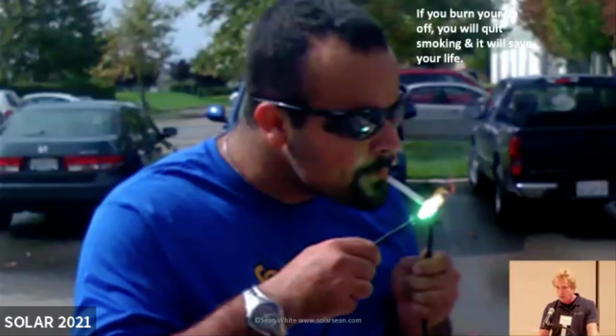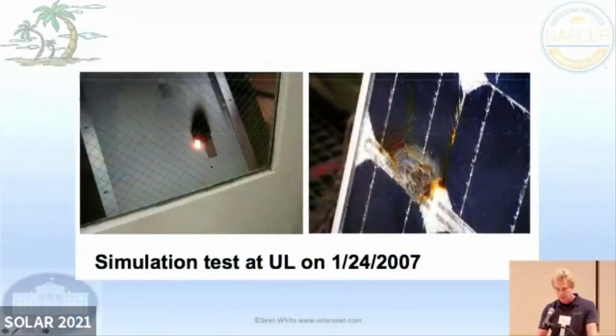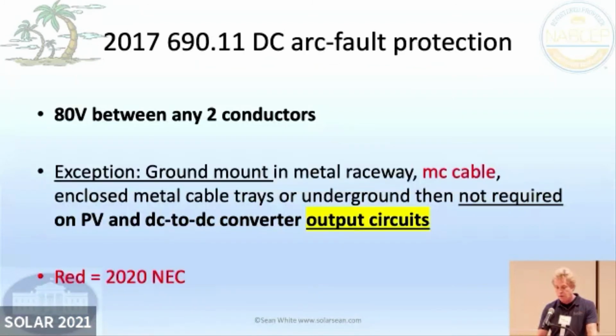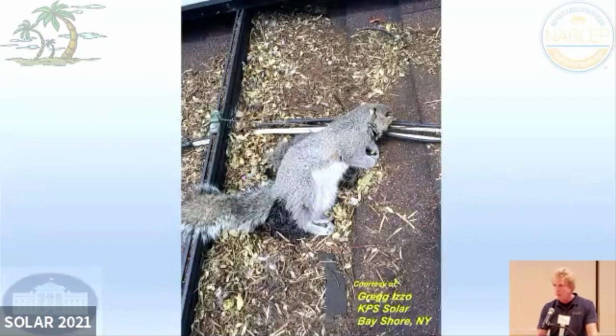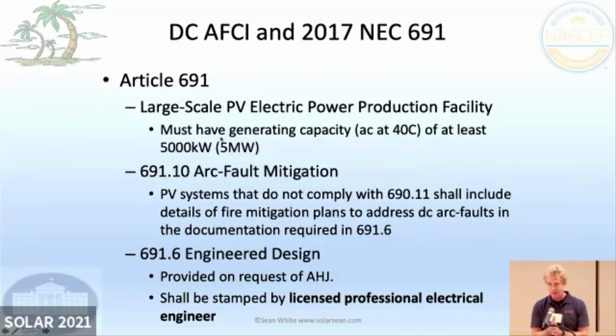We're talking about DC arcs. So that's a DC arc. Our inverters will see the signal of that arc, and then they'll turn off. You can see DC arcs can catch fire. So if there's an arc, an inverter will turn off the circuit. Our inverters have to have DC arc fault protection, but you can also train animals to do this too. So not everything is done with electronics, this is if you live in a cabin. What happened was there was a system, they installed it wrong, and there were too many leaves under there because the rail was installed too low, and then bad things happen. I know there are animal lovers here. I better just change that picture, sorry.